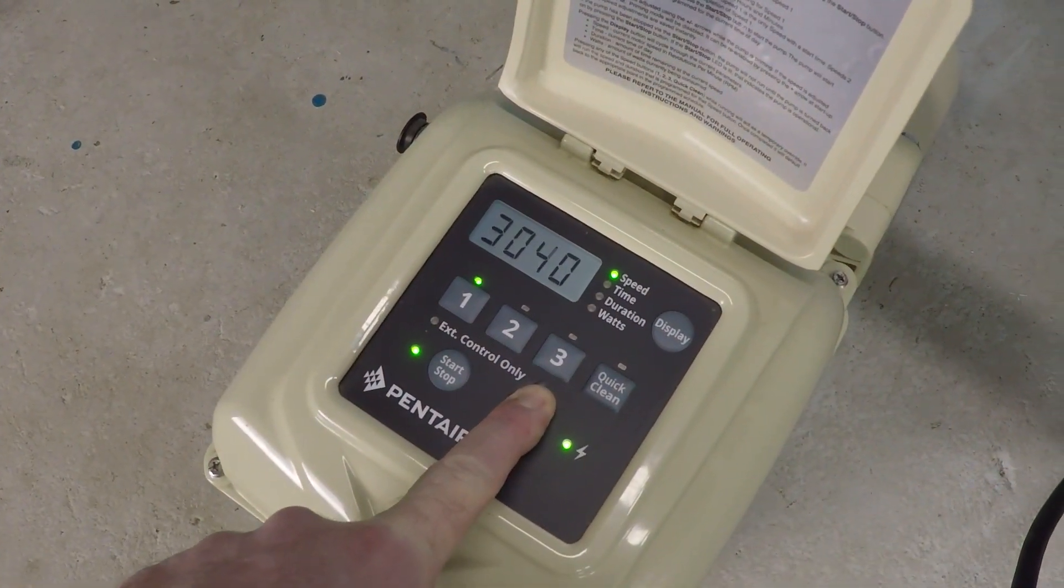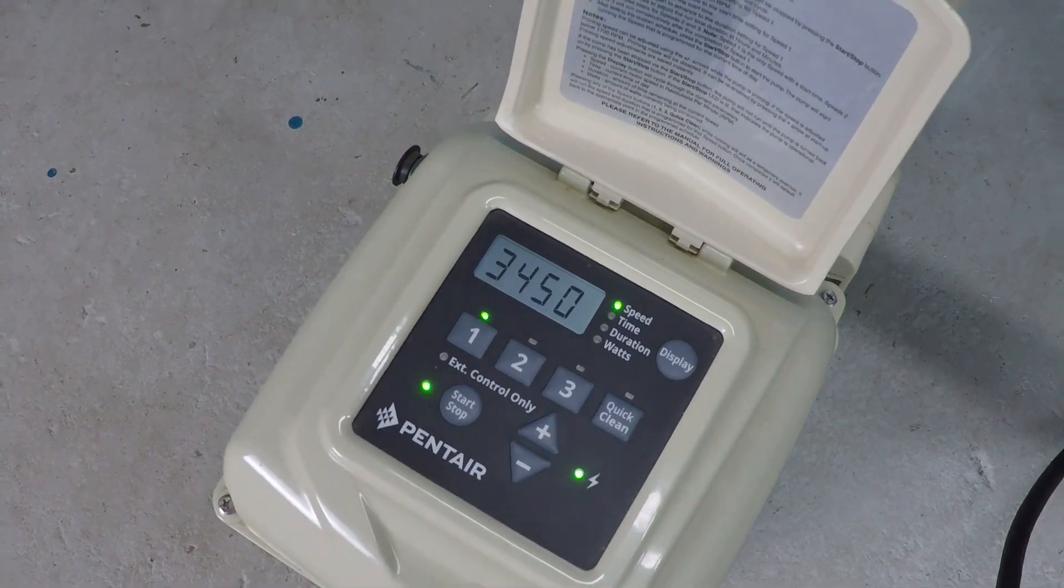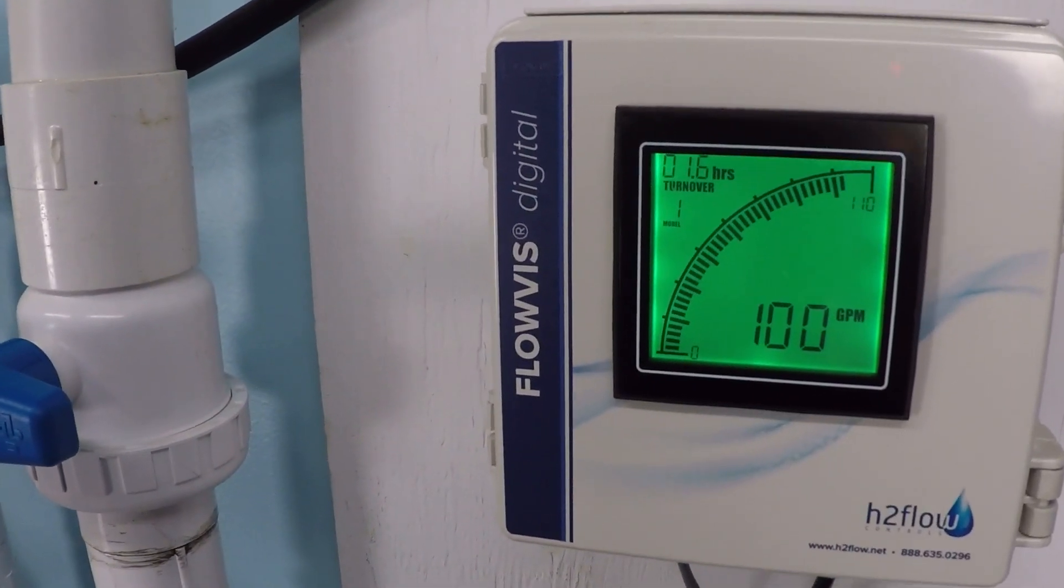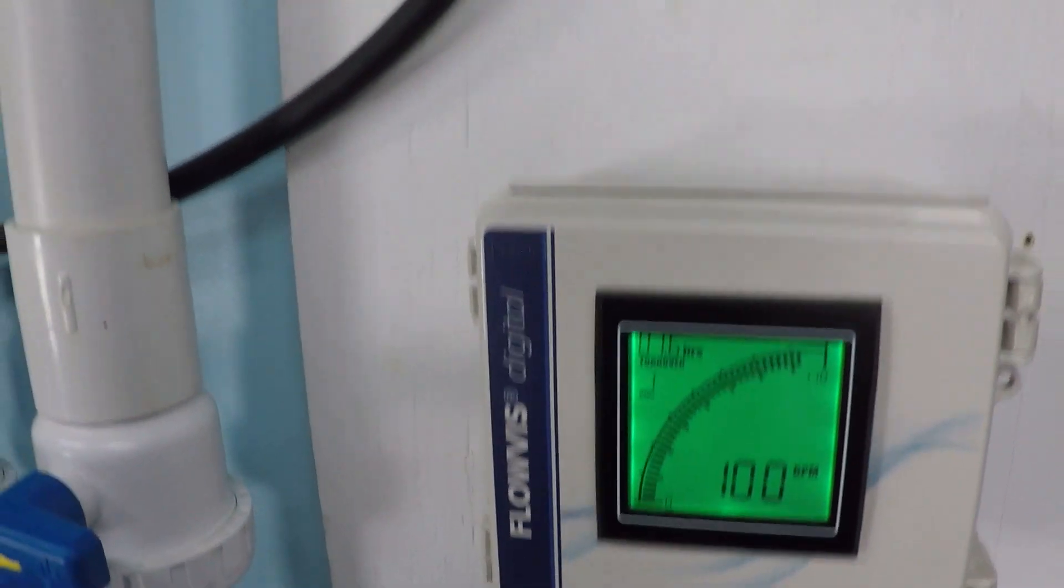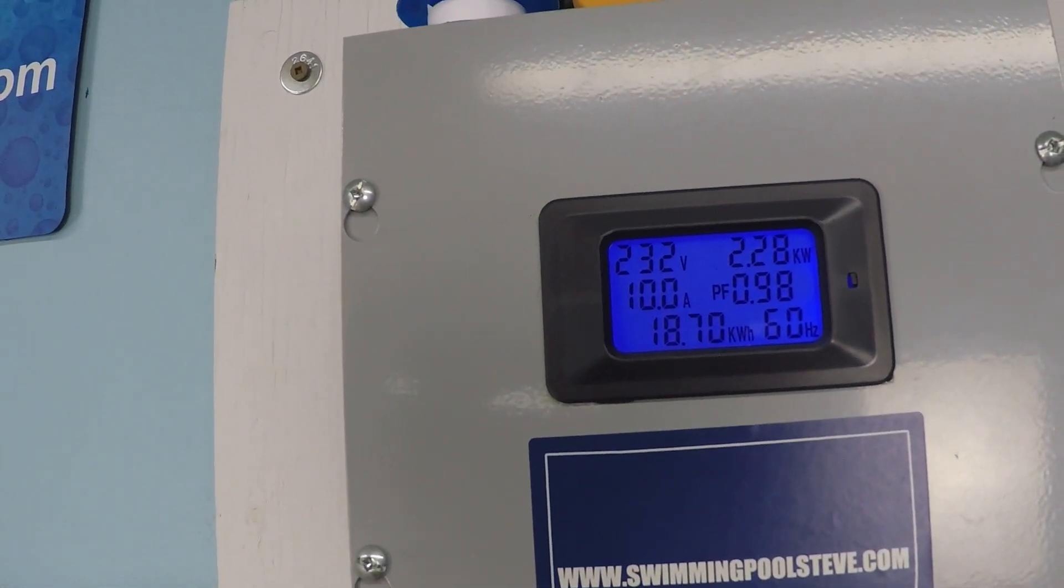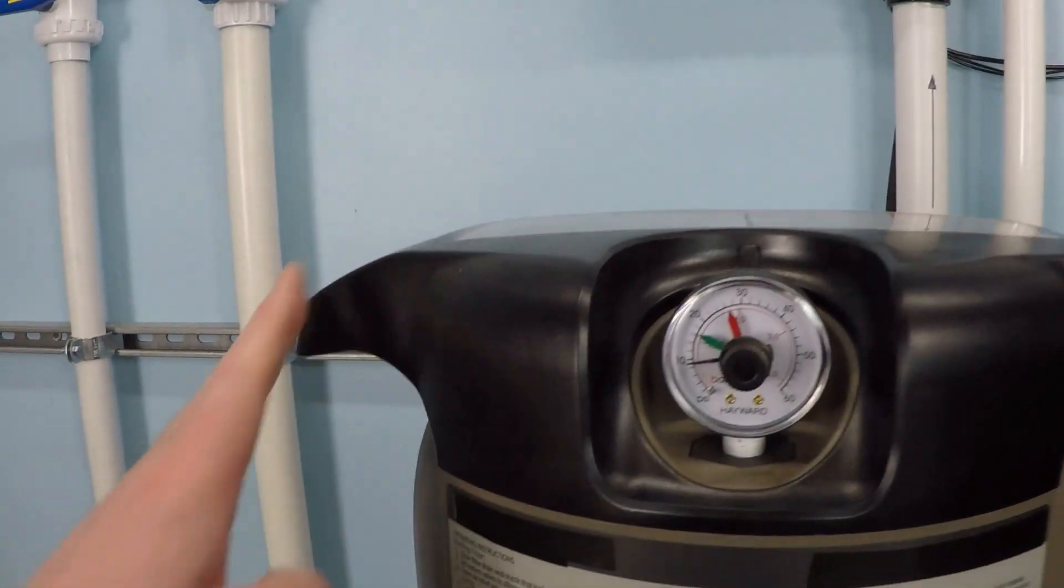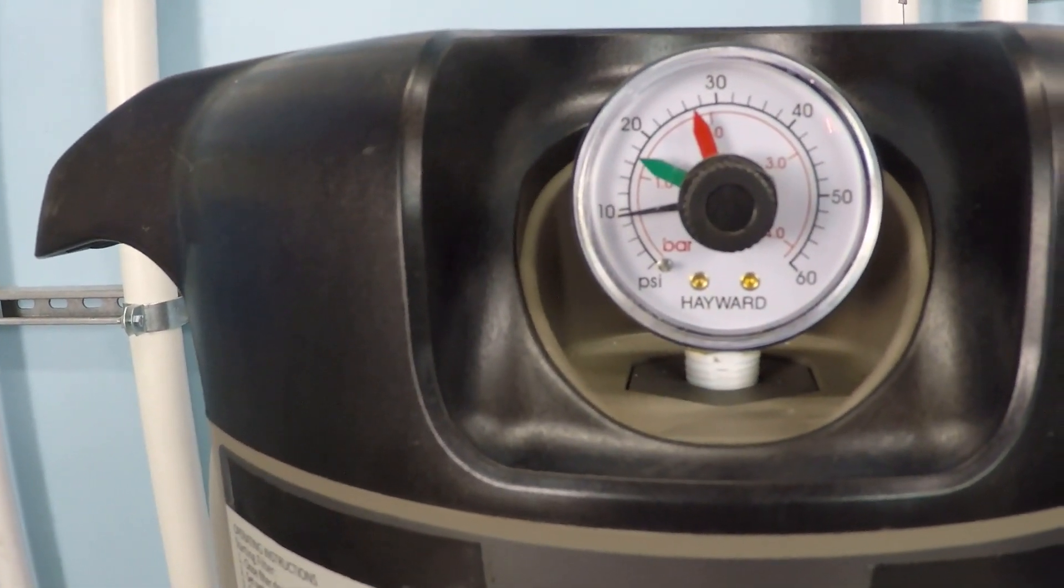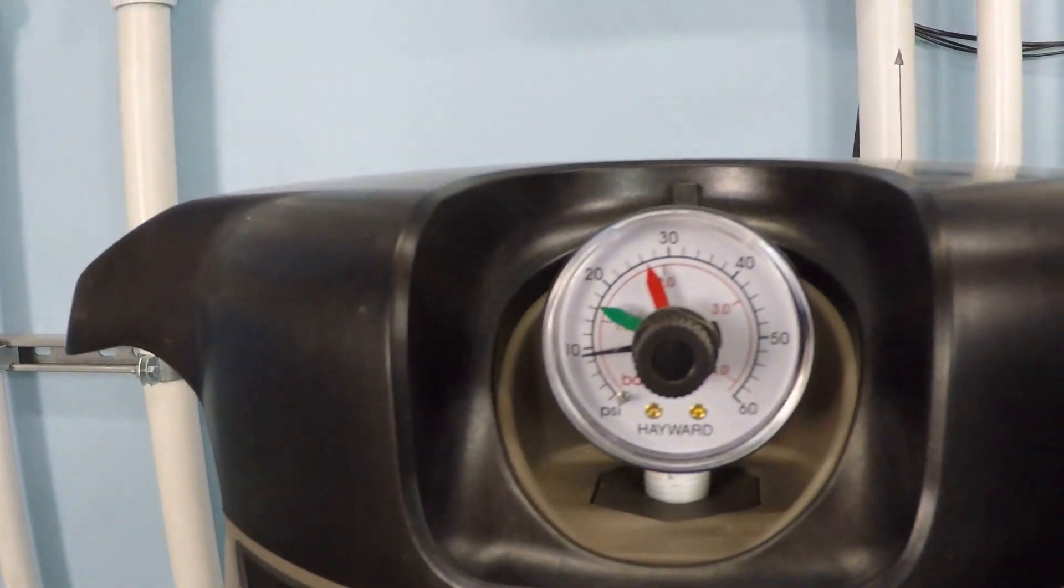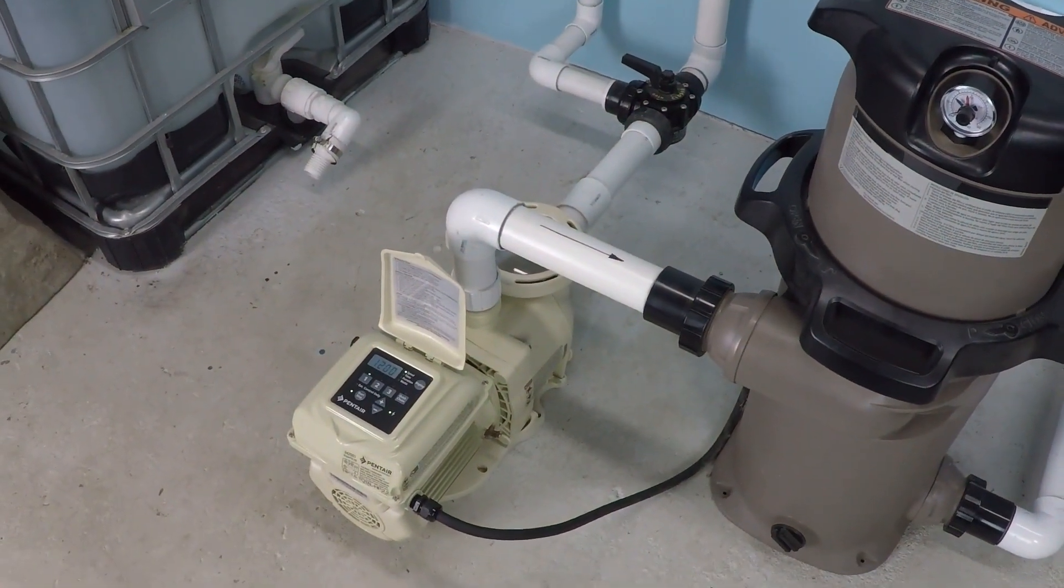And this will be top speed now. At about 100 gallons per minute, 2.28 kilowatts of power consumption. Now let's take a look at the filter to see our filter pressure. It's about 9.5 psi, and that'll be a good point of comparison here for when I hook up the second pump.